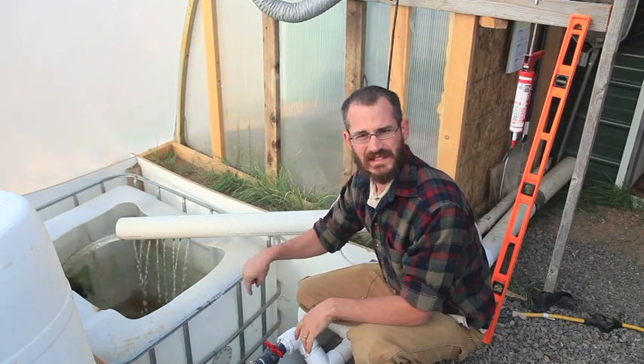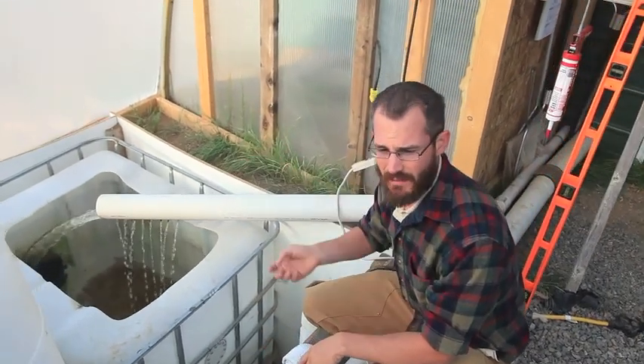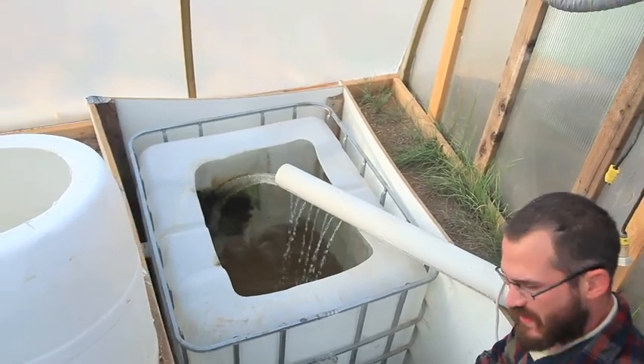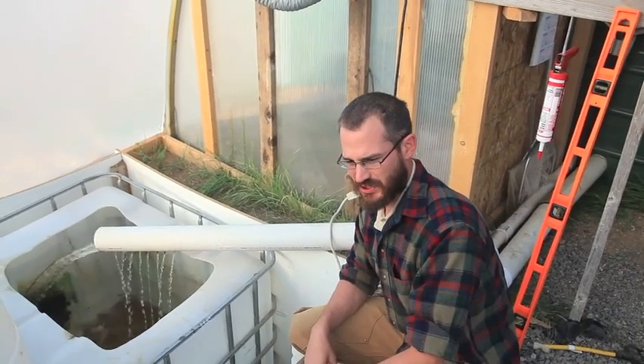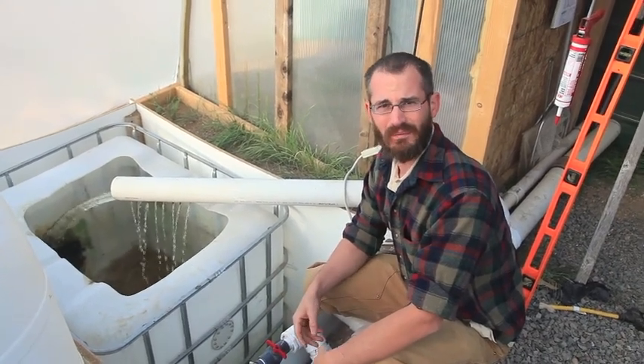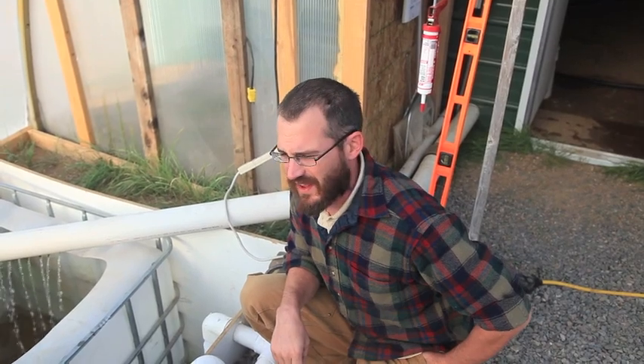We've also inset our pump down here so that we're not pulling water. If you're installing some of these larger pumps, you know that they don't draw water very well. By doing this, we're able to keep that pump down at water level and reduce the strain. If we run out of water or something crazy happens, we're not going to ruin our pump or put more wear and tear on it than necessary. This kind of setup works really nicely for what we're doing.